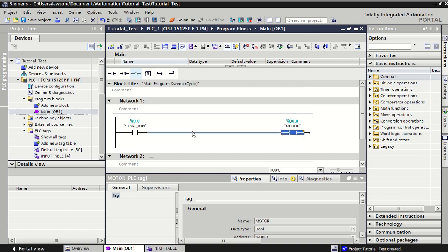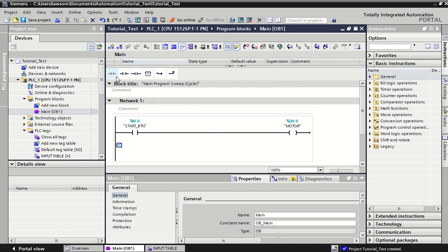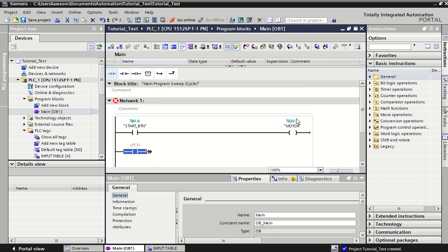Another great piece of code is what's called a latch, and the latch is super important. If you look at this line of code: if we push the start button the motor stays on, but if we take our finger off the start button the motor will turn off — which isn't ideal if we have to keep the button pressed to keep the motor running. So what we can do is set up what's called a latch. The latch uses the idea of using an output as an input, which may not make a whole lot of sense right now, but the PLC will know whether it has turned on that motor or not.